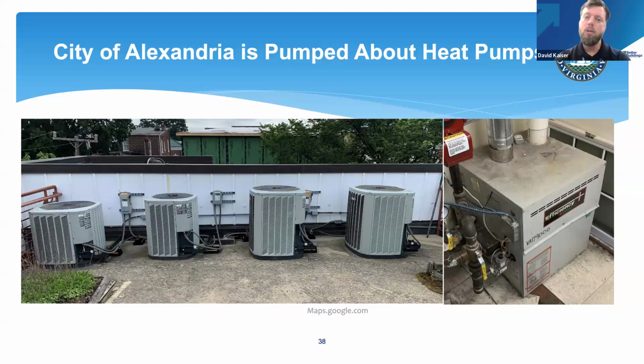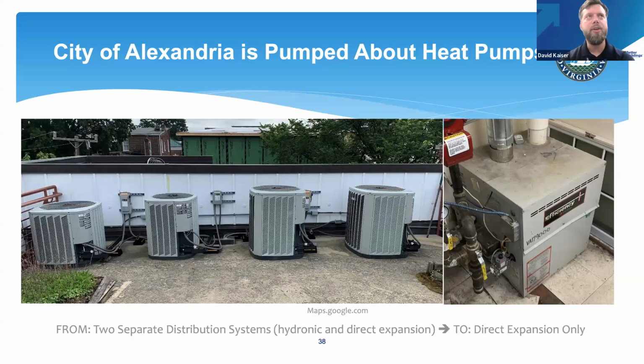And there can be cold climate heat pumps now that those are officially available. We can get high output at low temperatures. We can completely get rid of that boiler and rely on one distribution system. So one cooling plant at the roof provides heating and cooling through one distribution system. So now we have capital cost savings associated with not having to replace the hydronic system in this facility.